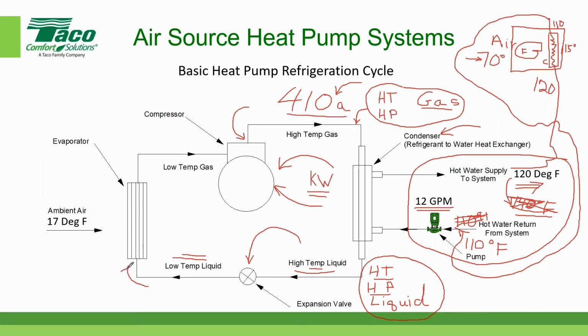Now here's where the fun starts. The temperature of the liquid has to be lower than the ambient temperature. So if the ambient temperature is 17 degrees Fahrenheit, the refrigerant temperature entering here might be, I'm just going to give you a number, it doesn't have to be this exact number, 0 degrees Fahrenheit. So the refrigerant is entering the evaporator as a liquid, and it's extracting heat from the air. Even though the air is relatively cold, 17 degrees Fahrenheit, the refrigerant is colder, so it causes the refrigerant to boil, because this temperature, 17 degrees, is much greater than 0 degrees.